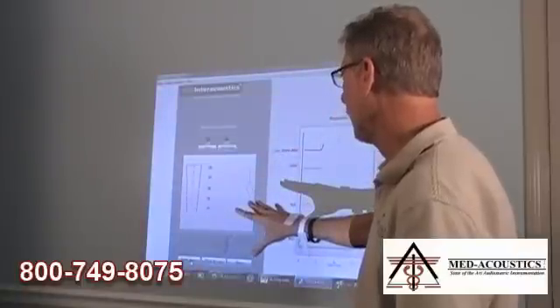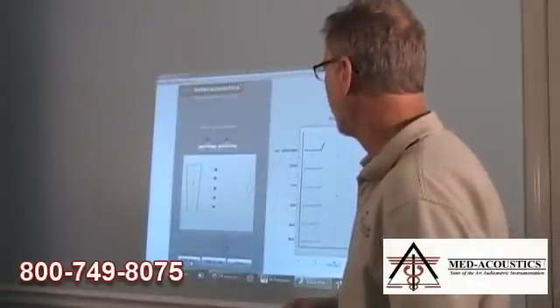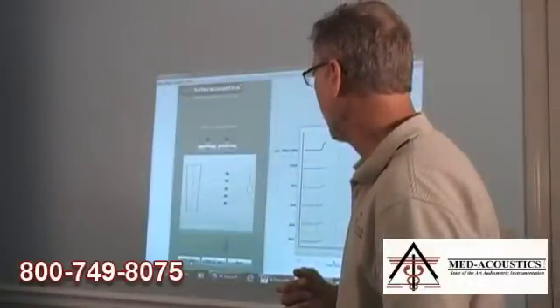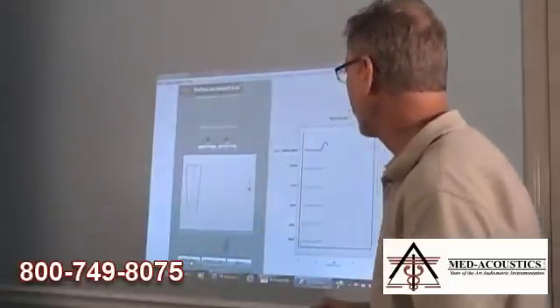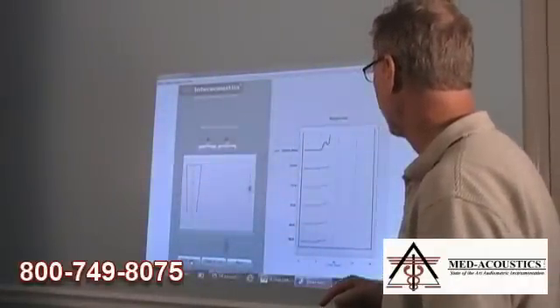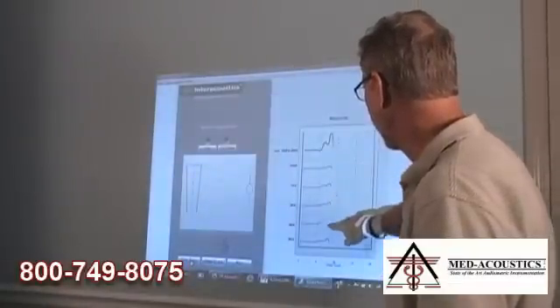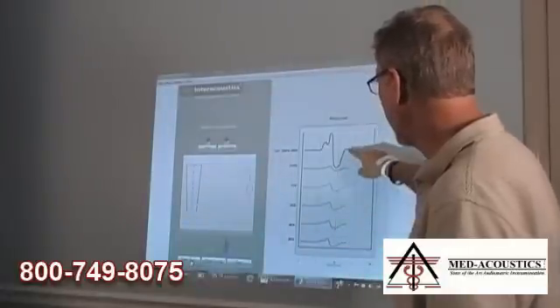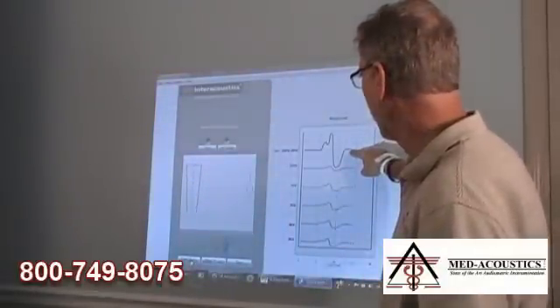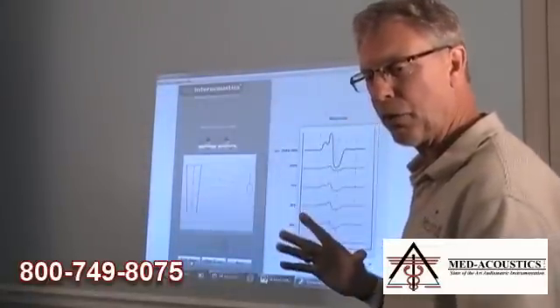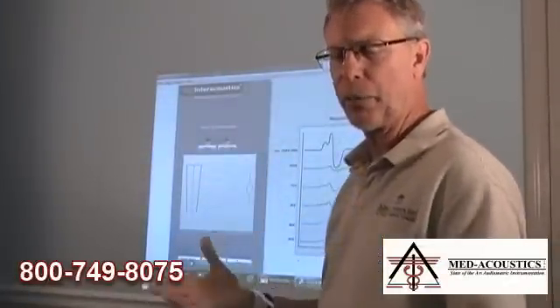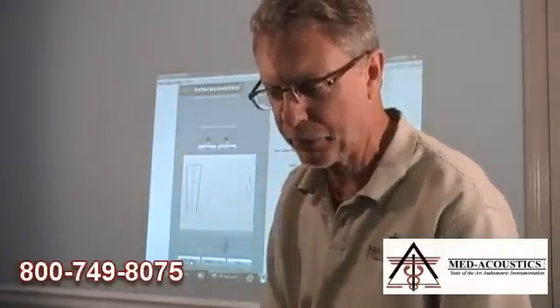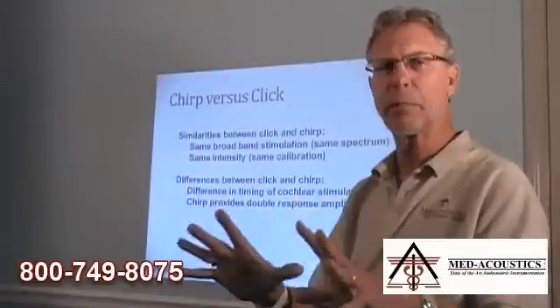They all fire at the same time. They all start heading down the auditory nervous system at the same time, and they all arrive at the inferior colliculus — the generator of wave 5 — at the same time. So wave 5s are all generated simultaneously. They line up, and the final waveform, which is the addition of all of those, is twice as robust a wave 5 than we had with the click. I hope that demonstrates the efficacy of how it works in overcoming the timing problem within the cochlea.